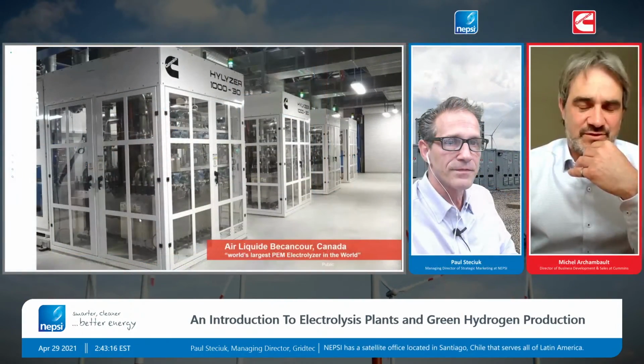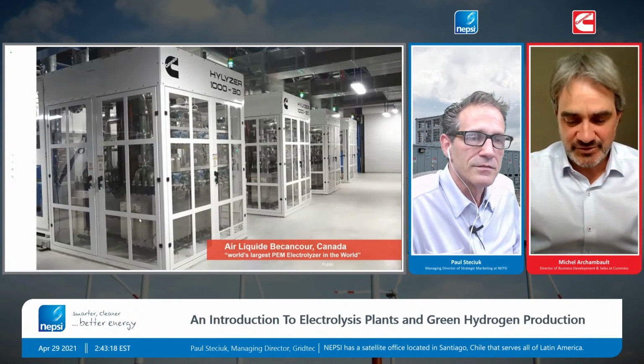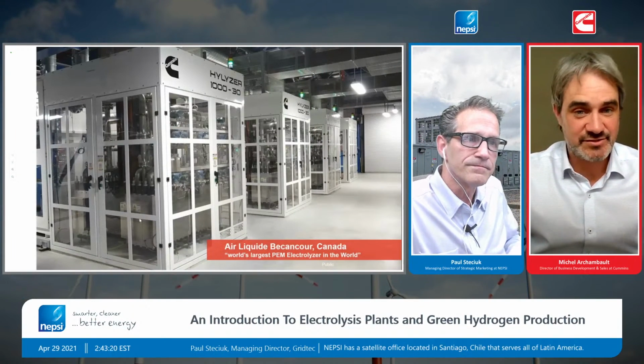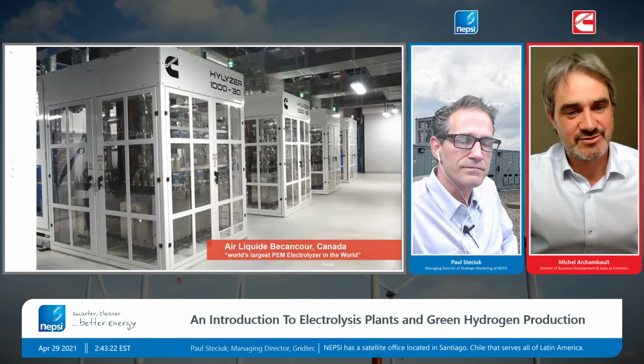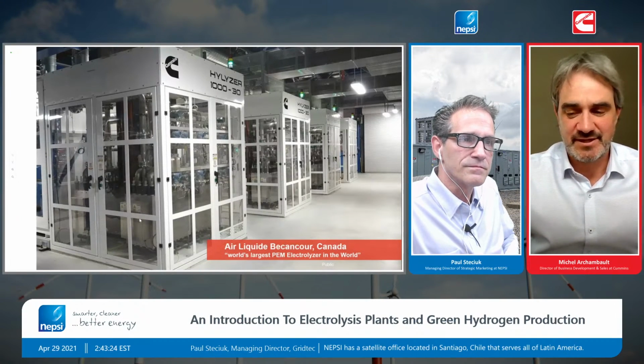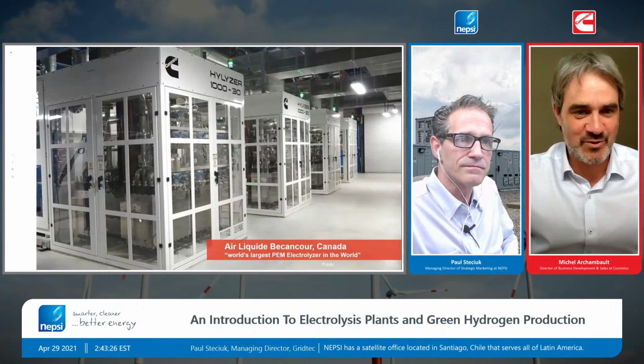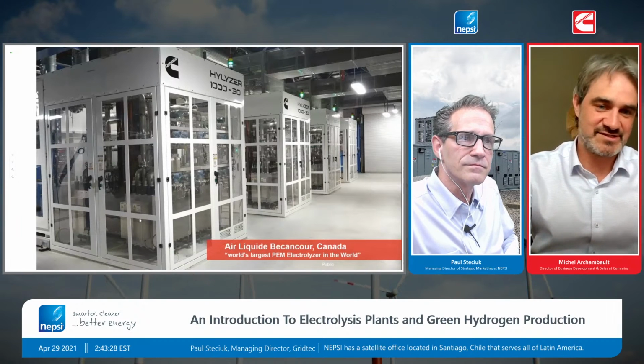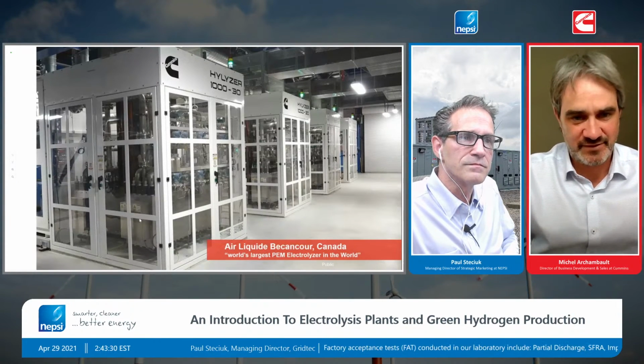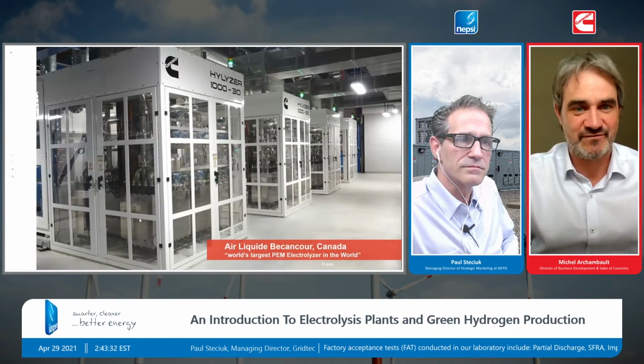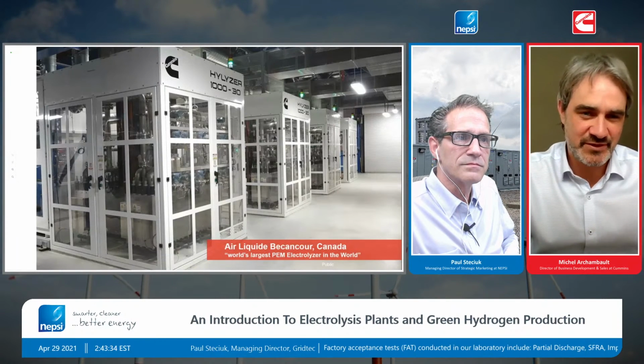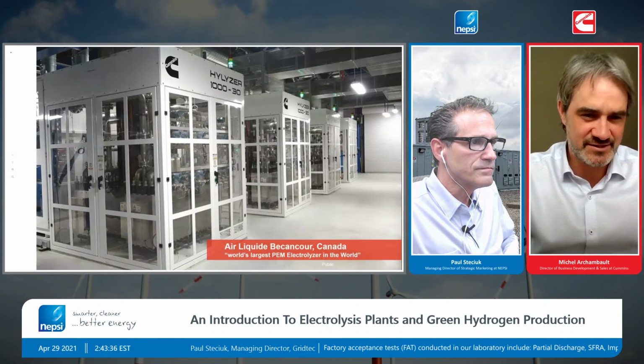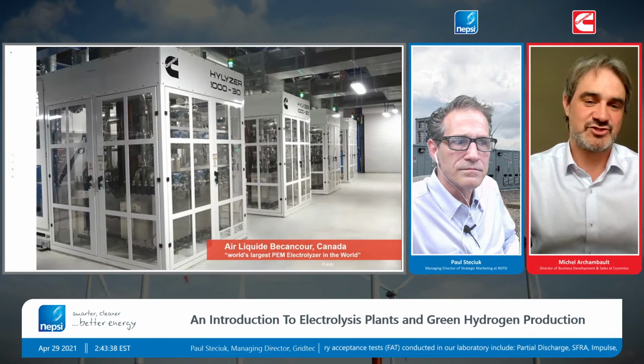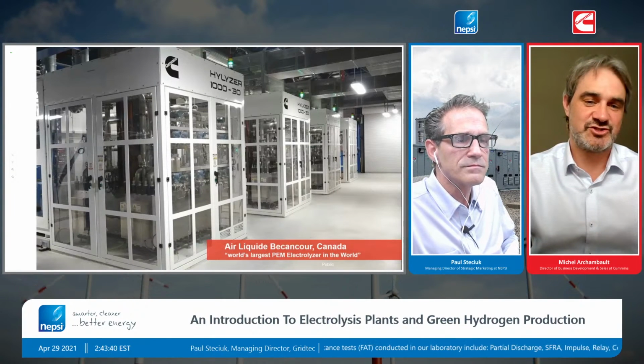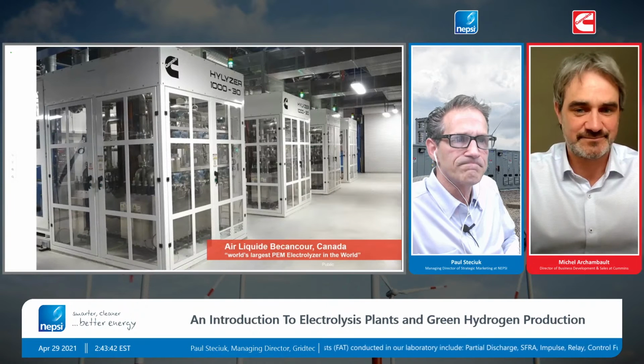These electrolyzers accept medium voltage power, ranging anywhere from 4.16 to 30 kV approximately, and that's how we work. You bring the power to 4.16 to 30 kV, we take care of it at that medium voltage range, and we feed and distribute the power. You see the bus bars here, and we feed the stacks and distribute the voltage evenly across the stacks.